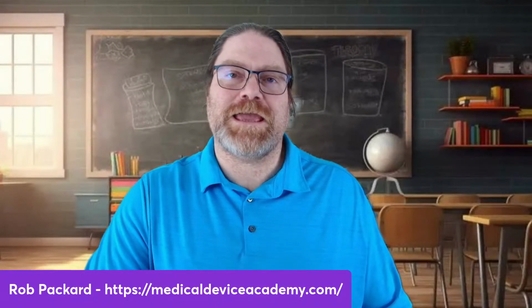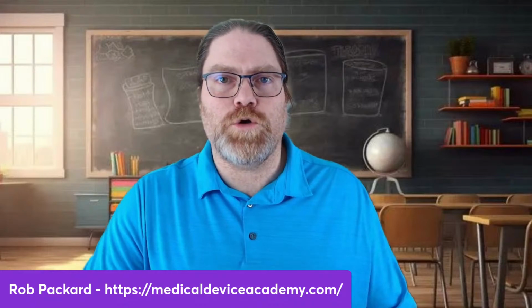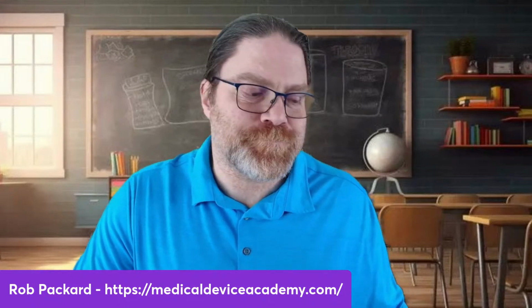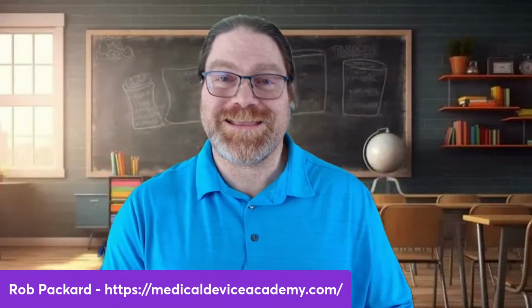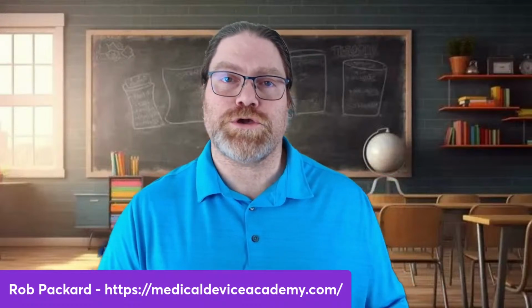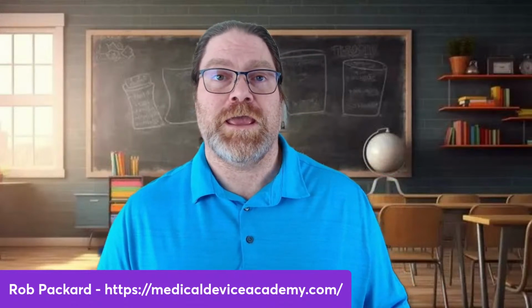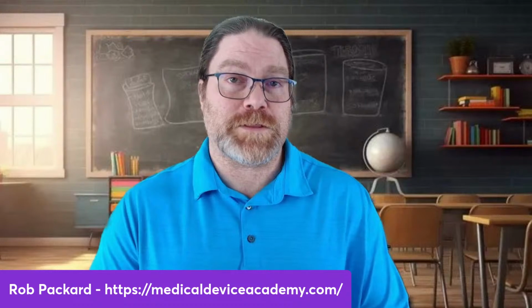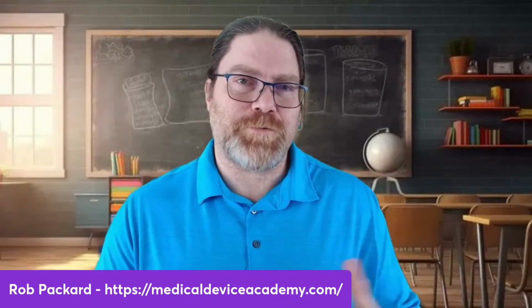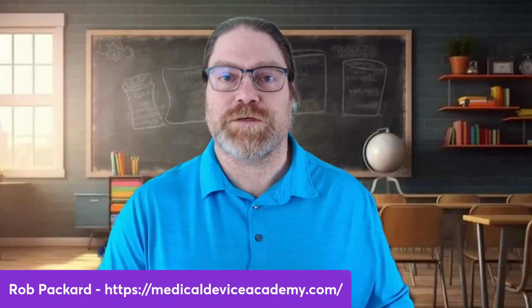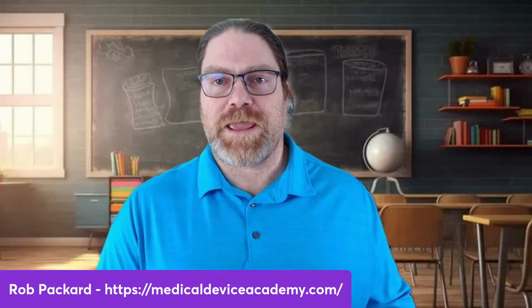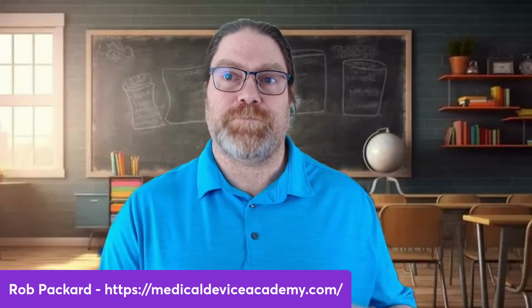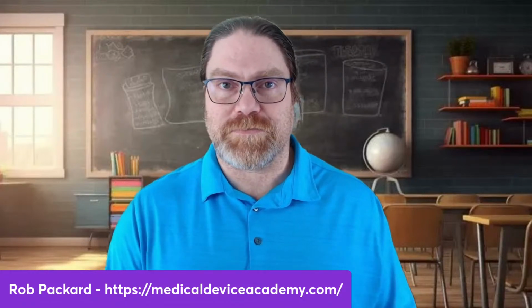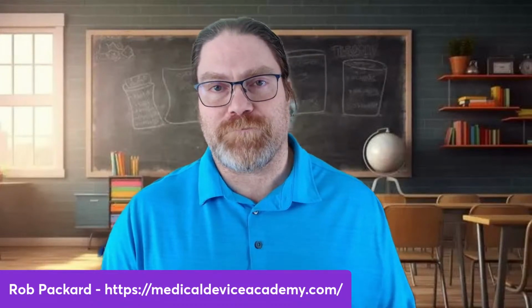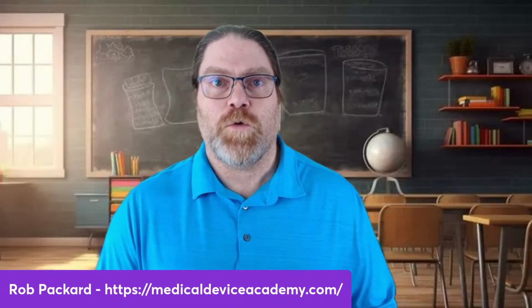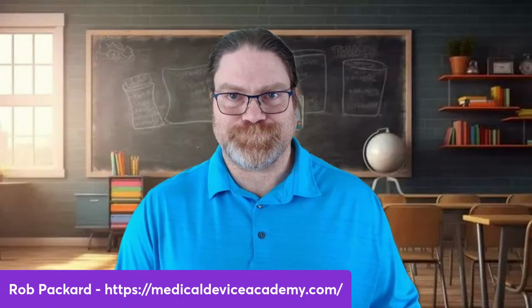Do you have any idea what IQ, OQ, and PQ stand for? IQ is installation qualification, OQ is operational qualification, and PQ is performance qualification. And I've heard a couple other variations of those three acronyms and what they mean, but those are the three acronyms that we use to describe the three traditional parts of process validation that is used by the medical device industry and the pharmaceutical industry when you have automated equipment.